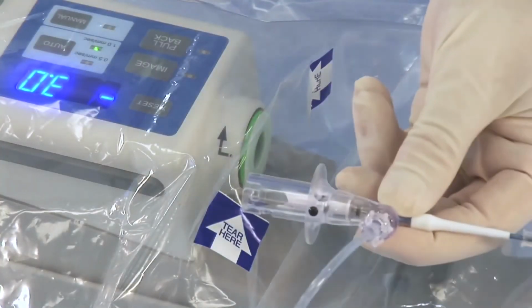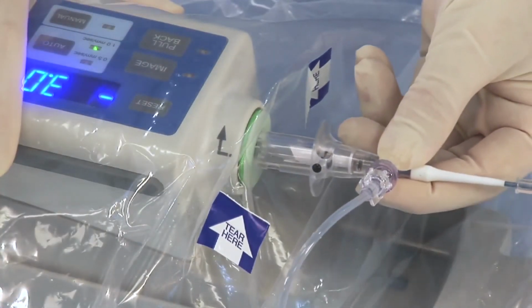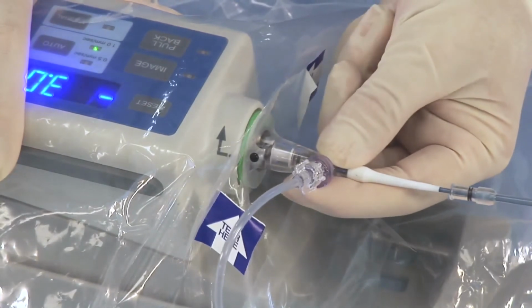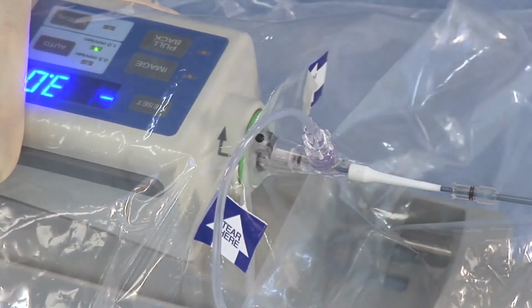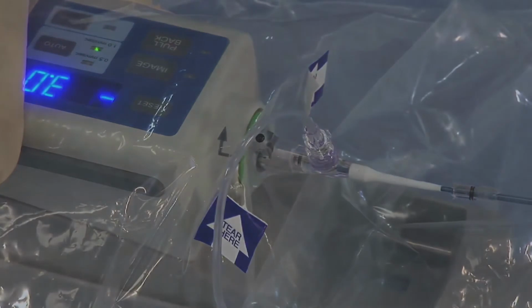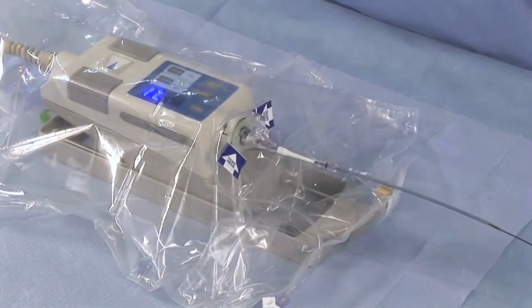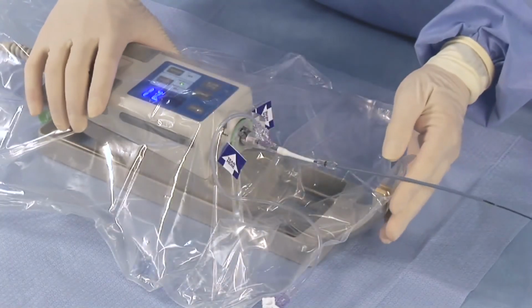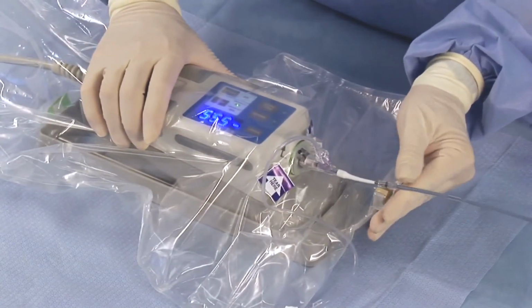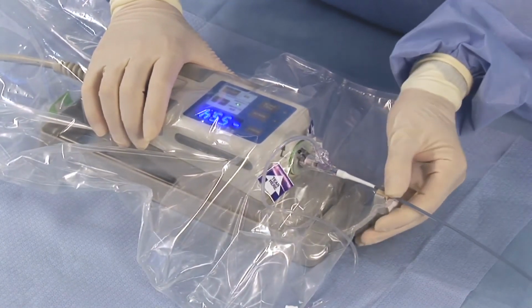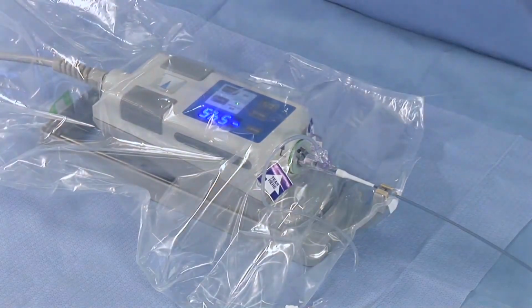Insert the prepped catheter into the device by aligning the black dots on the catheter and device. Then turn to lock the catheter into place. Note: take care to avoid opening the telescope section of the catheter at this step. This could introduce air in the system and require reflushing the catheter prior to use. Ensure the sled is advanced completely forward. Then secure the catheter onto the sled arm, using the hub on the proximal telescope shaft.